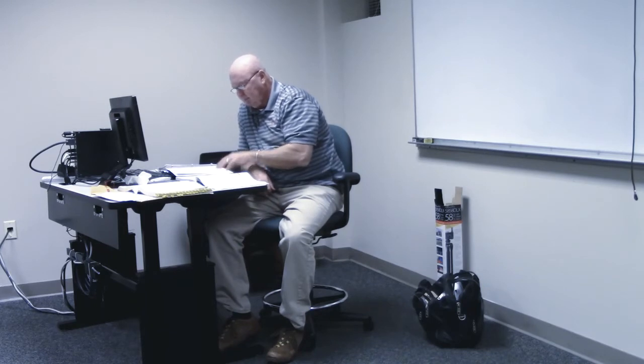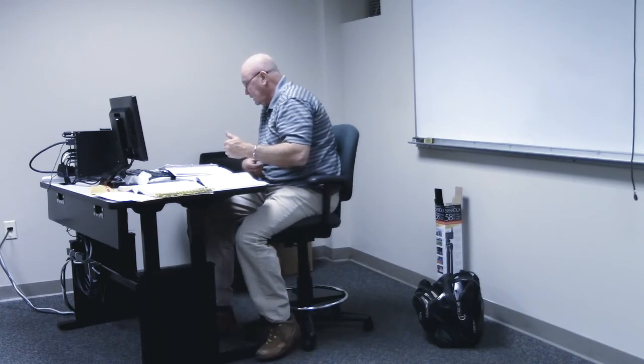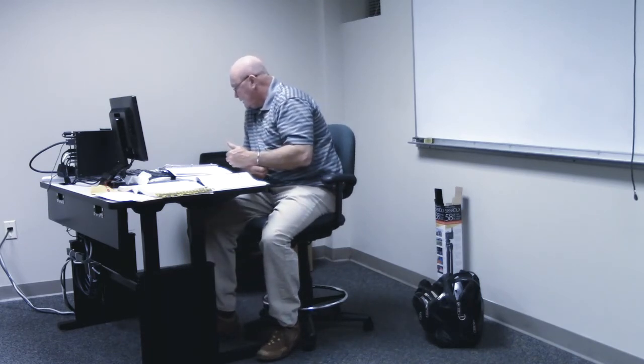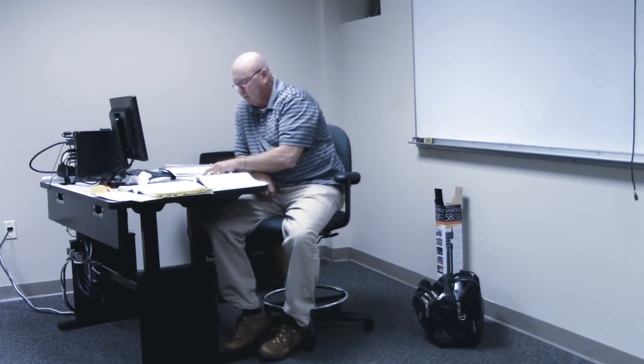Critical branch: if we look here at the picture, number 3 on page 3, you see that block up there? We see EES, we've got an alternate source, which is something like an emergency system. We see three different groups there: an equipment branch, a critical branch, and a life safety branch. The biggest thing I want you to know about a critical branch is that it's related to patient care. So I just write that out to the side of it. Critical branch, that red little square there, is related to patient care.